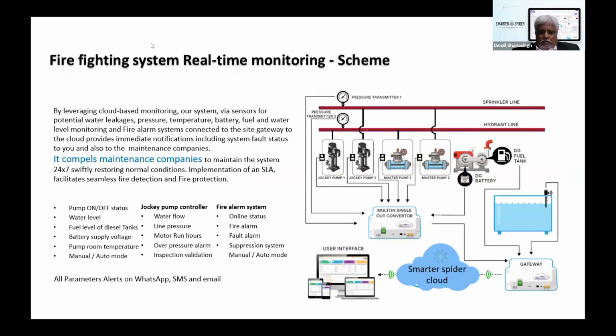So this is your schematic, which just shows where the sensors are installed in a firefighting system. You have the jockey pump. Some sites can have multiple jockey pumps, master pumps, and the diesel pump. So all these pumps, the pressure levels, the temperatures, everything are taken into a multi-in single-out converter, which is connected to our gateway. And the gateway is connected to the smarter spider cloud. And from the cloud, you access it from any of your digital devices.